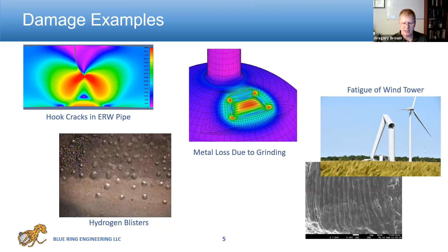Now in 579, as well as other fitness for service standards and even inspection codes, you're going to see very often what's called a level 1, 2, and 3 assessment. The idea is that this would be the escalation you do when you encounter damage. A level 1 assessment is designed to be very conservative, designed to be something quick, so very often you're looking up on a graph or figure whether that equipment is safe to operate.